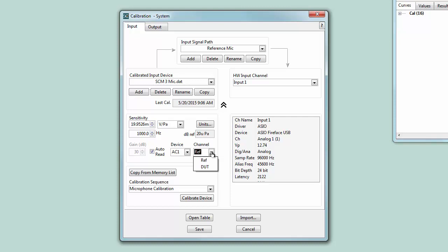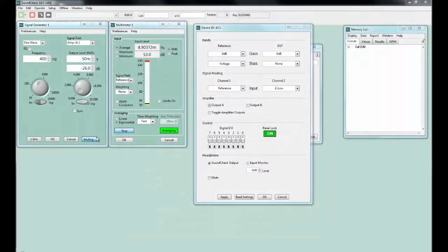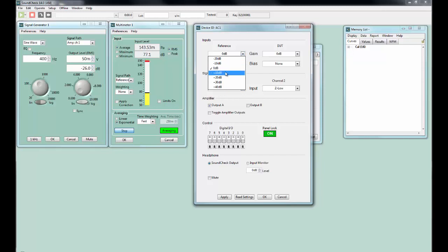In the example shown here, a simple measurement is being performed with the virtual instruments. As the gain of the AmpConnect preamp is adjusted, the calibration editor is tracking the changes and applying the updates. The result is that the multimeter is always accounting for the current gain setting and is showing the calibrated level.